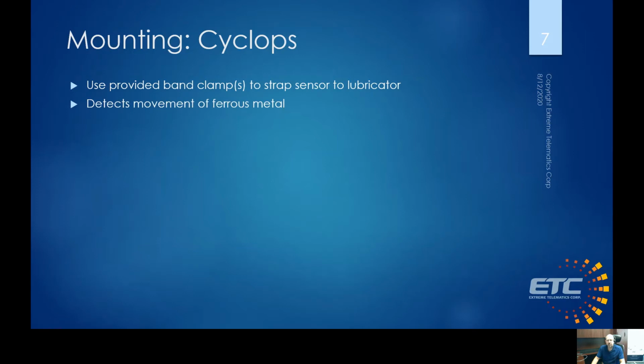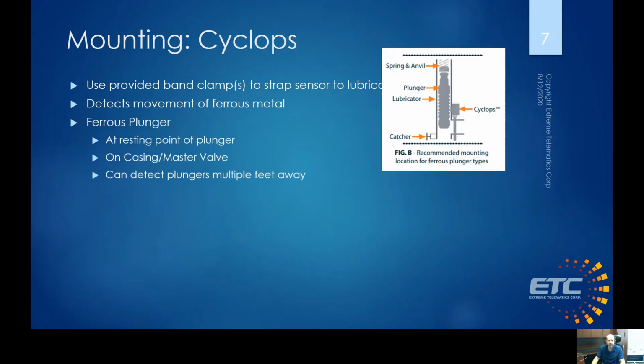In general, the Cyclops looks at the movement of ferrous material. A piece of metal that goes by the sensor actually bends or pushes and pulls the magnetic field of the Earth, and it's that deflection that we're looking for to determine an arrival. So if you're using a ferrous plunger, you can just put it at the resting point of the plunger. As long as the plunger gets close to it, you'll actually see that bending of the Earth's magnetic field.